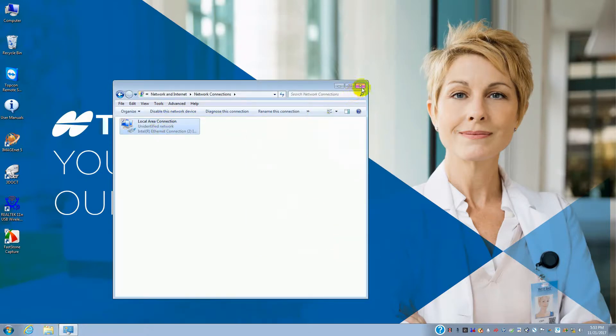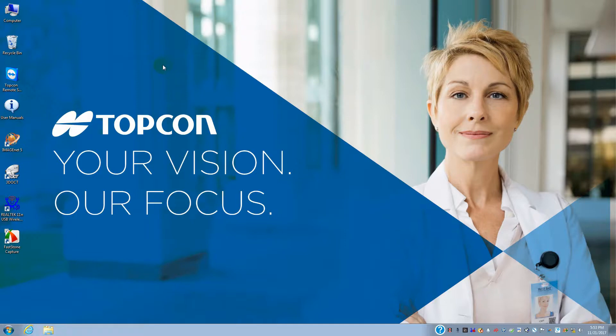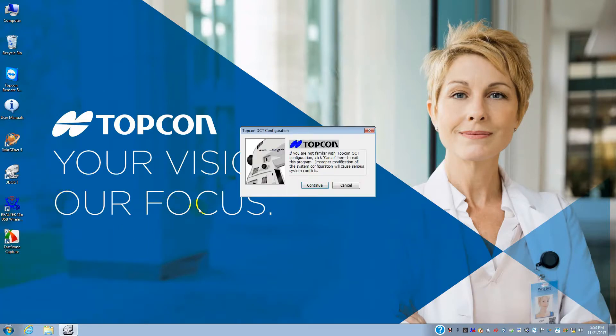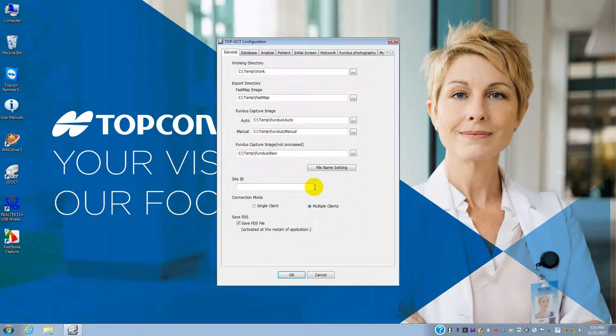There's one other thing you have to do — you have to make sure that same address of the OCT is in the right spot. Go down to the Start button and go to OCT Set, click that. You'll get a Topcon prompt — click Continue — and the OCT Configuration menu will come up with all the tabs. Click the one that says Network.